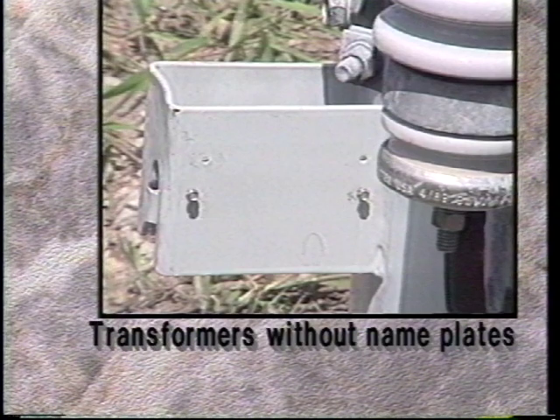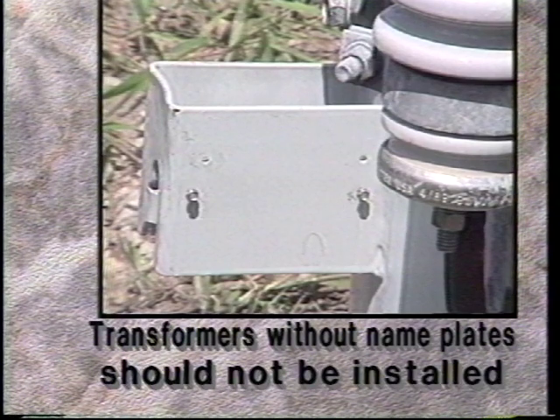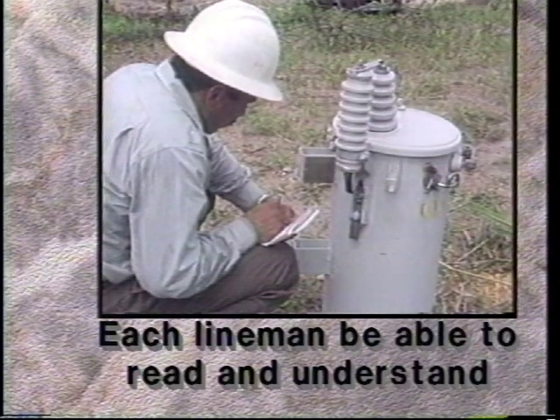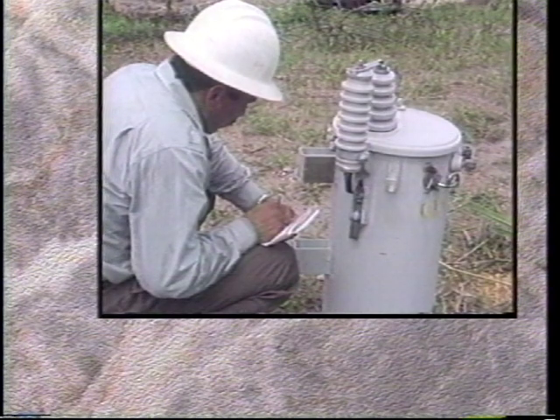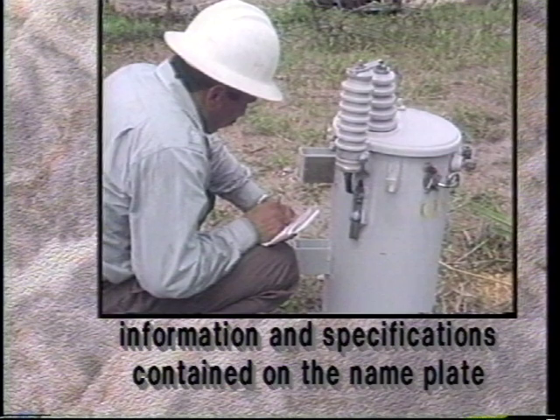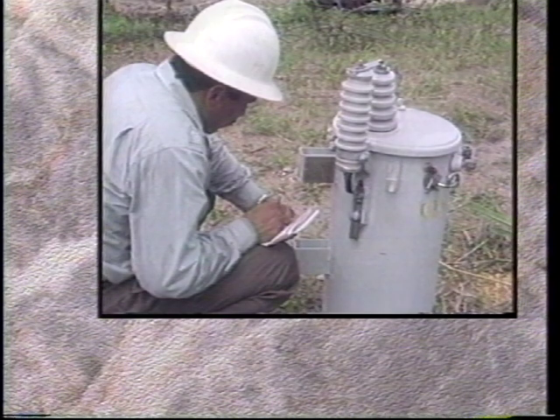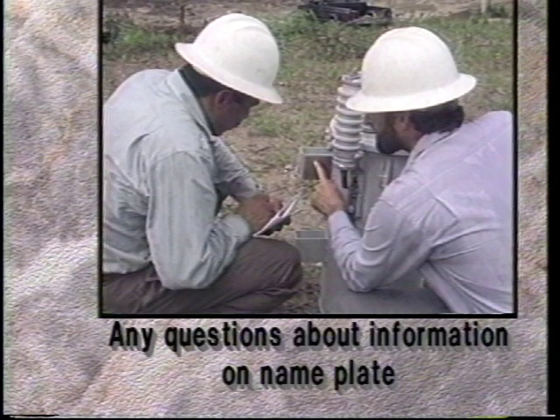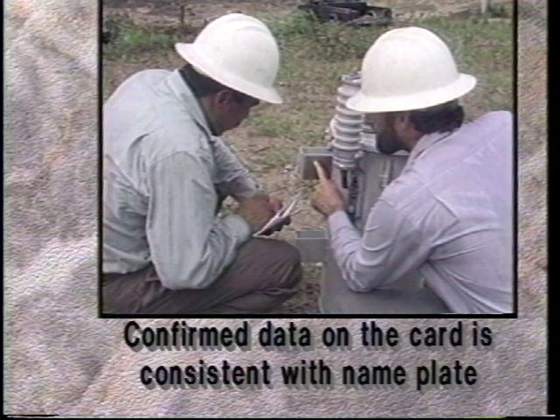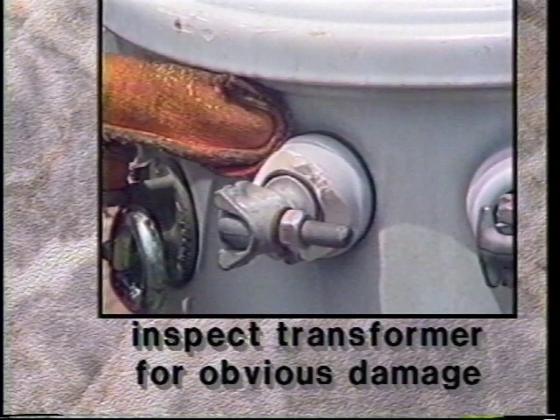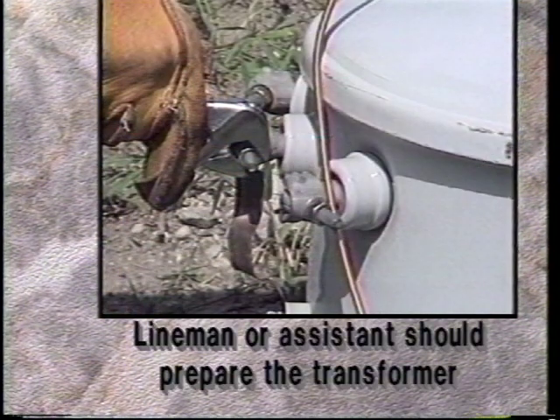Warning: transformers without nameplate should not be installed. It is important that each lineman be able to read and understand the information and specifications contained on the transformer nameplate. In case you have any questions about information contained on a transformer nameplate, consult your supervisor. Once you have confirmed that the data on the card is consistent with that on the nameplate, inspect the transformer for obvious damage.